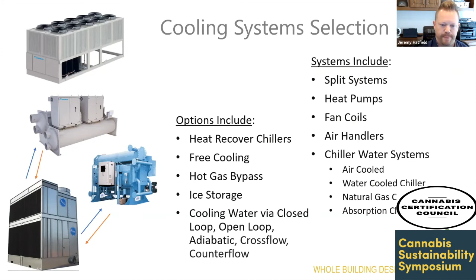You really need to keep that in mind, otherwise you'll end up with a lot of supplemental dehumidification, which frankly seems to be very common. That supplemental dehumidification adds to your power demand and adds capacity requirements to your cooling system. As you look at these different systems, be sure to check the options available—you may like heat pumps, but you might not get the advantage of free cooling that you'd get with air handlers and air-side free cooling. Just keep that in mind.